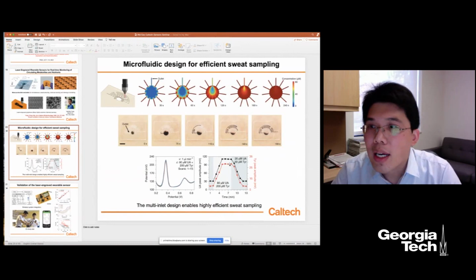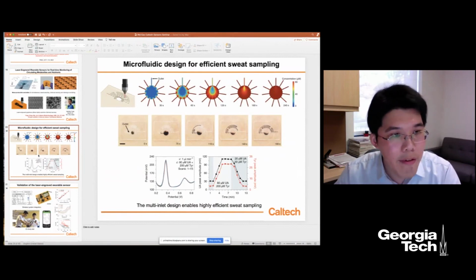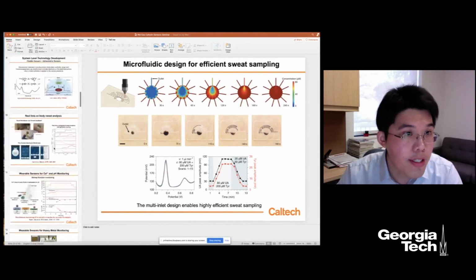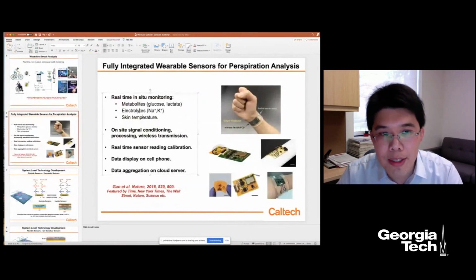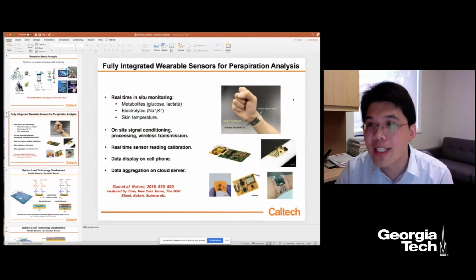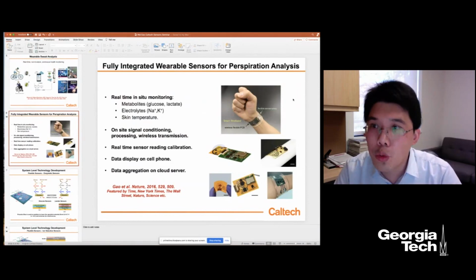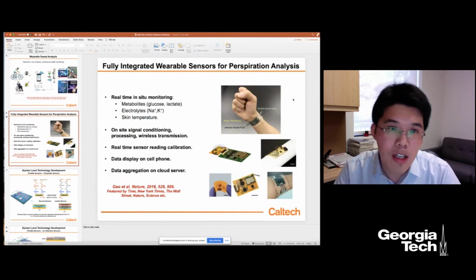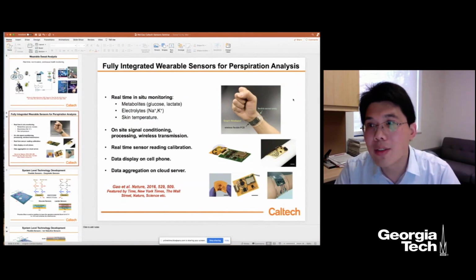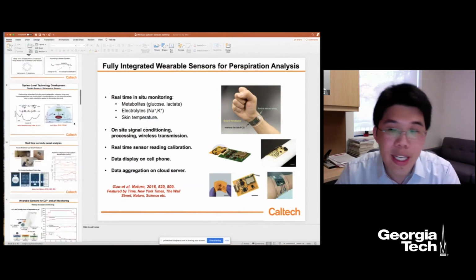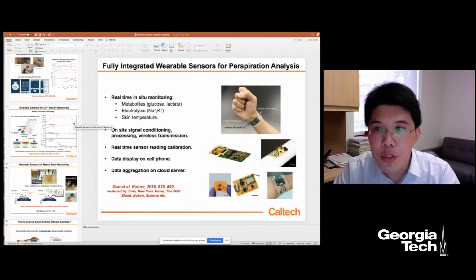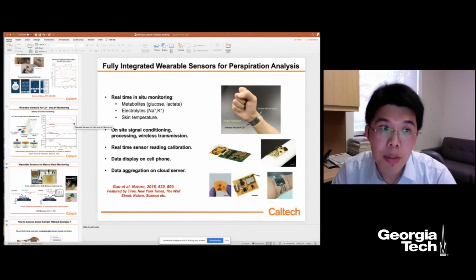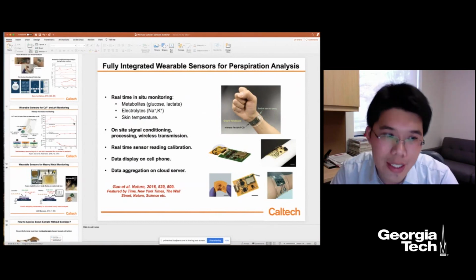Regarding calibration, certainly sweat biomarker or sweat sensor readings could be influenced by temperature, for example, and potentially influenced by sweat rate. So we actually have a temperature sensor. If you remember in my first example, from our first batch, we already included a temperature sensor. In all our wearable sensors, we have a temperature sensor on board. You could read the temperature in real time to do the real-time sensing calibration. Depending on the biomarker, some will probably need more calibration to get a better correlation. As I demonstrated, we already get a pretty good correlation on many biomarkers. By introducing more calibration mechanisms, such as sweat rate calibration, potentially we could get even better correlation, because some biomarker levels will be influenced a bit by sweat rate, how fast you sweat.